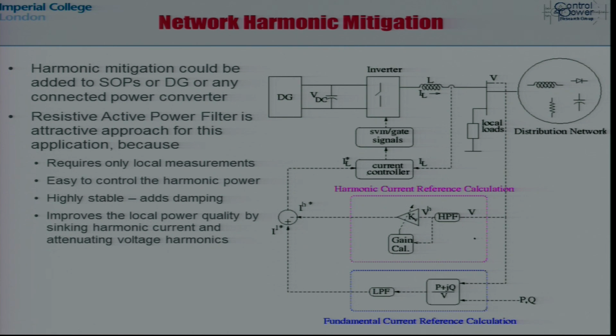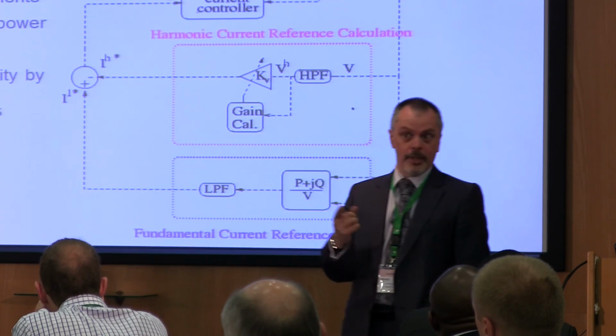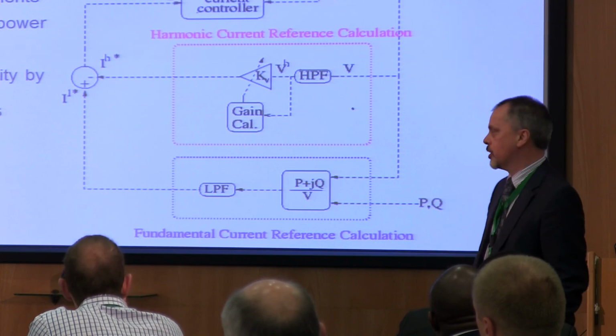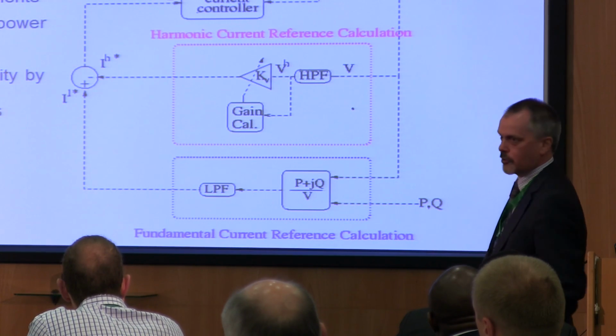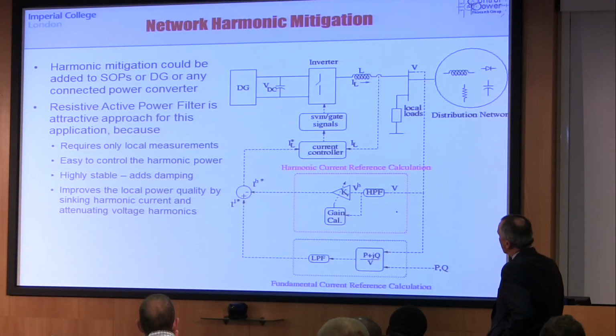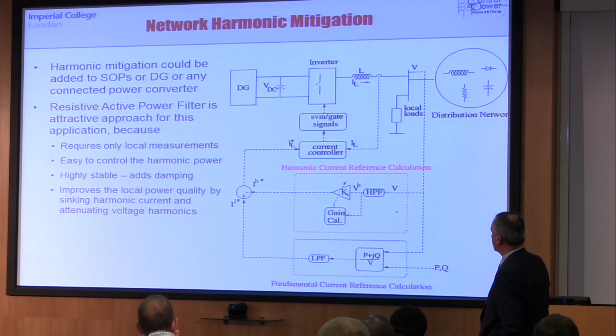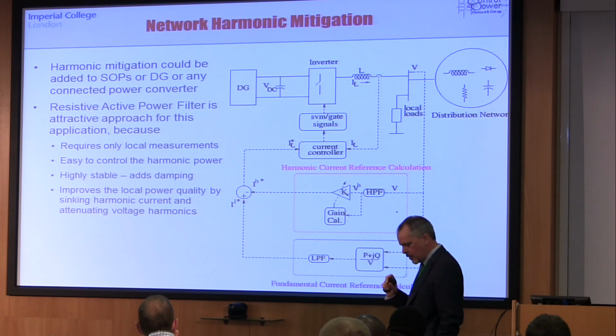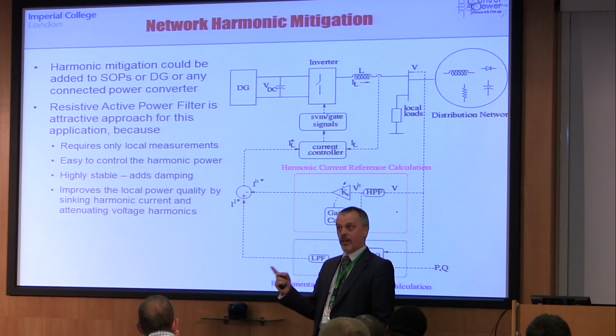I think the heat pump study in particular taught me that if you have a collection of heat pumps that only just comply with IEC 61000 and you accumulate them on the feeder, then you're quite quickly into voltage limits, particularly on the low order harmonics. So I think there is a case for doing some harmonic mitigation, and I quite like the idea of doing it through emulating resistors at the harmonic frequencies.